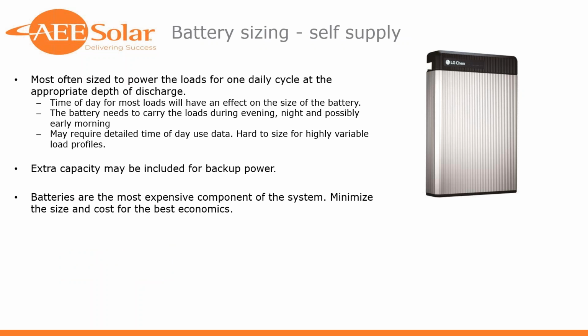Well, self-supply is a little different. It's a similar concept to off-grid, but it's grid tied and you're serving a different purpose. You're trying to just even out the solar over the day so that during the evening when you're using power and there's no solar available, you can use the solar power that you saved over the day in the other parts of the evening and night. And for this type of use, you really are generally sizing the battery just for the single day cycle at the appropriate depth of discharge.